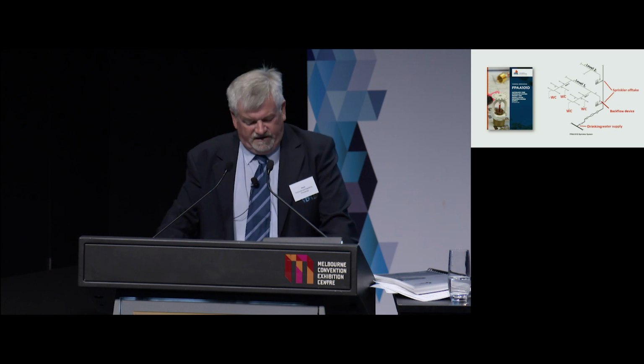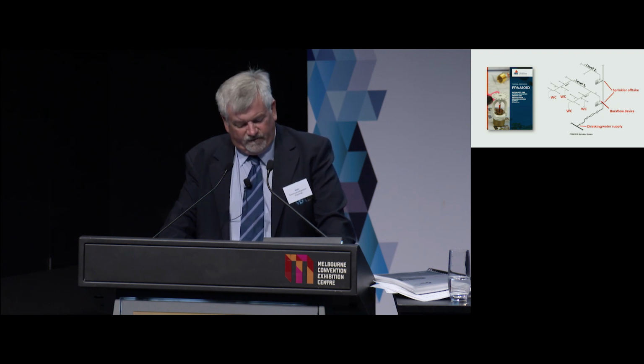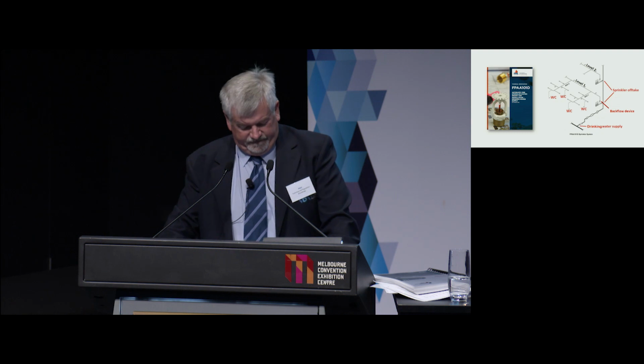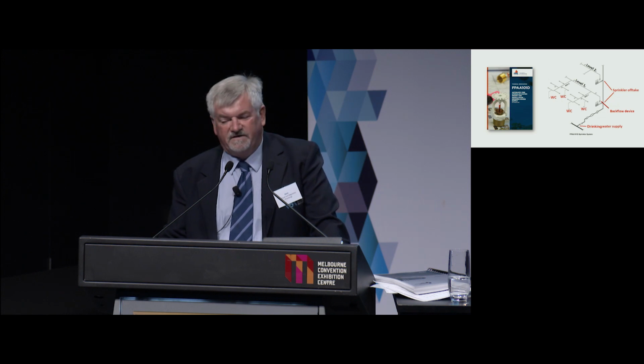The first standard is FPAA 101D, Automatic Fire Sprinkler System Design and Installation from Drinking Water Supplies. It is used for systems that are fed by the drinking water supply and are connected so as to supply water to the toilets in each unit. FPAA 101D indicates that all components downstream of the backflow prevention device on that supply, including sprinkler heads, must be watermark approved. So the entire piping system, including sprinkler heads on a combined system, is required to be watermarked.